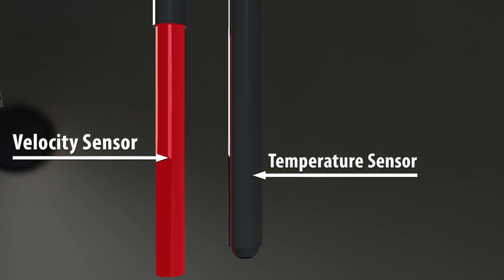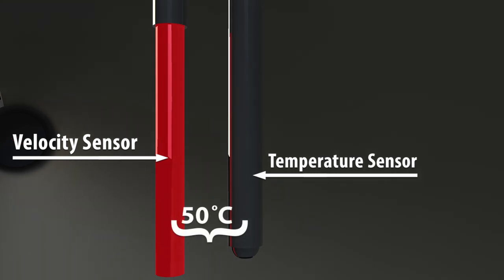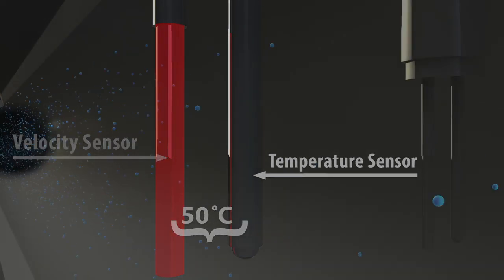As the name implies, thermal dispersion mass flow meters use heat to measure flow. The velocity sensor is heated continuously via electrical wattage so that a predefined temperature differential is always maintained between the two sensors. For example, 50 degrees Celsius is the constant temperature differential for Sierra meters.